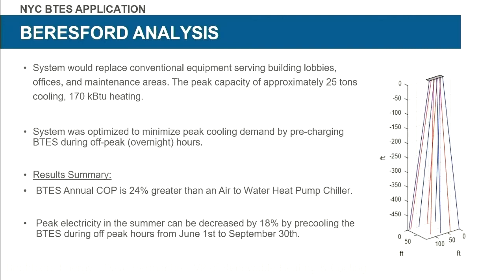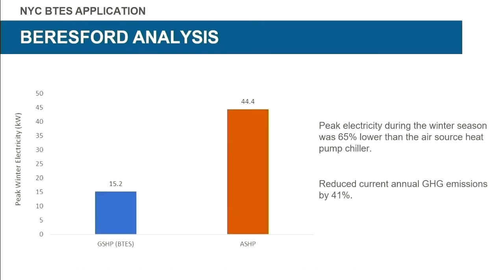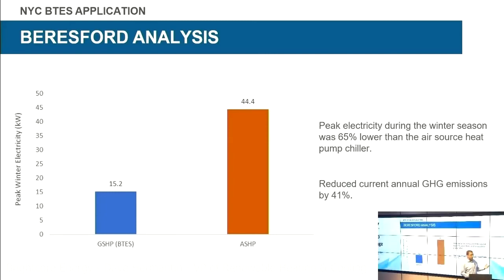It also provides all the benefits of ground source for a coefficient of performance, just very high COPs during heating. And what I like to illustrate is that during heating, this system is about 64% more efficient than an air source solution. So it's quite dramatic. The COP for a system like this hovers around 4 during the coldest days of the year.